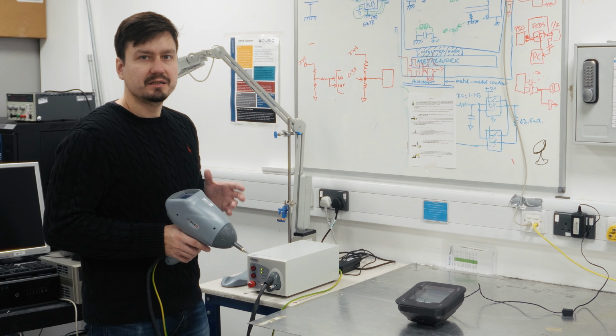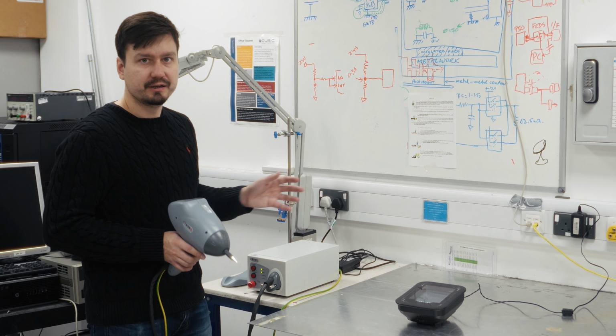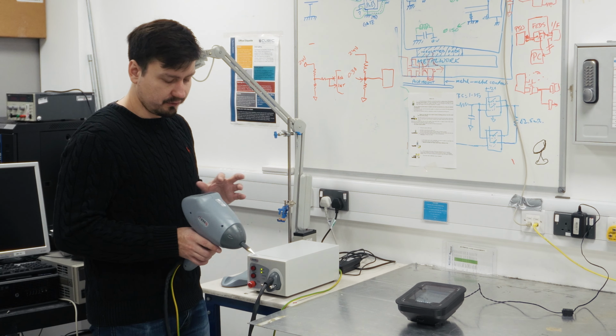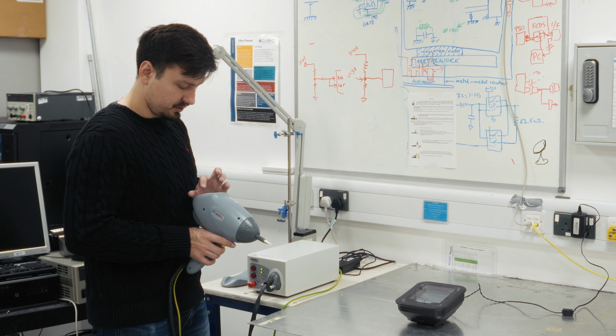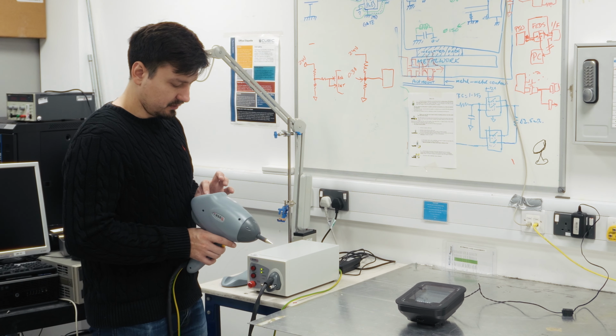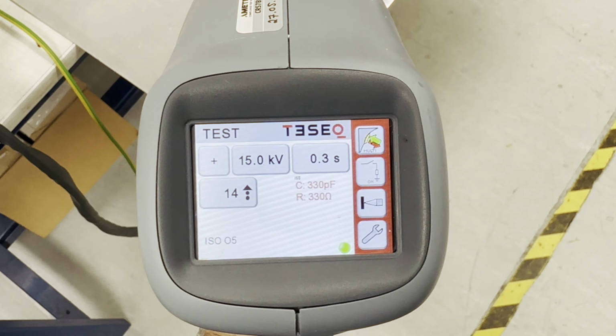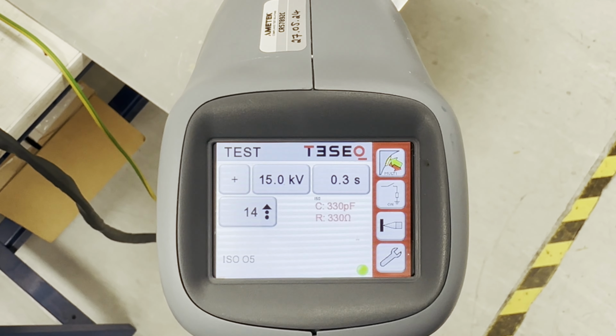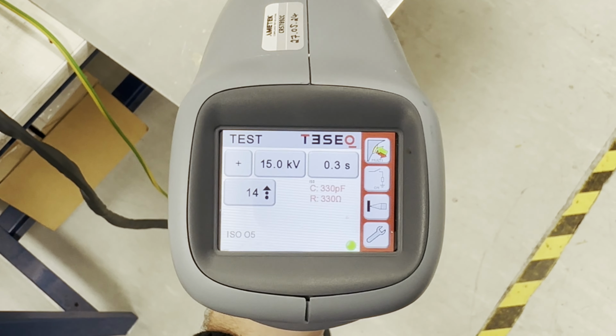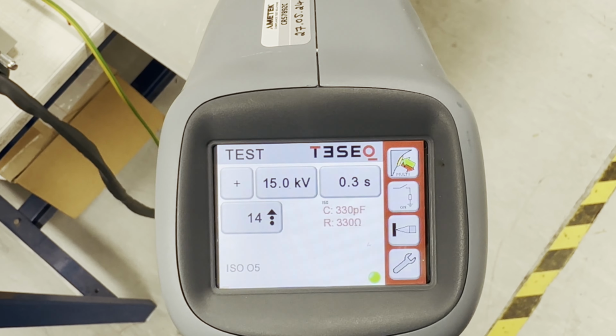So now I'm going to increase the test voltage for the coupling plane to 15 kilovolts. At the moment I was using just 4 kilovolts. Make sure to always use exactly the right tip characteristics that you're actually using. And now I'm selecting 15 kilovolts. If you look at it like this on a screen, you can see the tip capacitance and tip resistance and the voltage selected. And also the discharge time is as per the ISO 10605 standard. So now I'm going to discharge it holding my hand into the coupling plane. Yeah, see, now there's big sparks going.